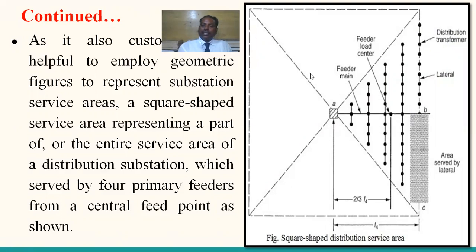Yes. So this is a substation center point, and this feeds the 4 primary feeders. Coming from the transmission and stepped down in the substation with the help of high power transformers, there are 4 feeders which are going to the various load centers. So 4 feeders you see here. This is the one feeder for serving the loads A, B as well as C.